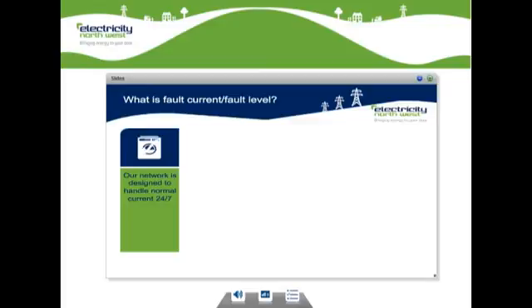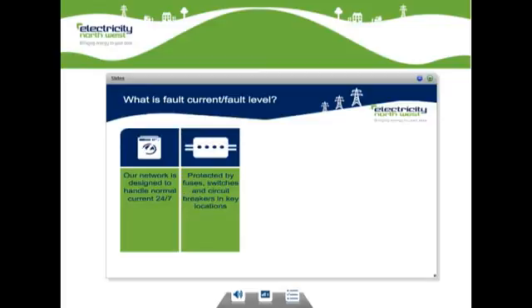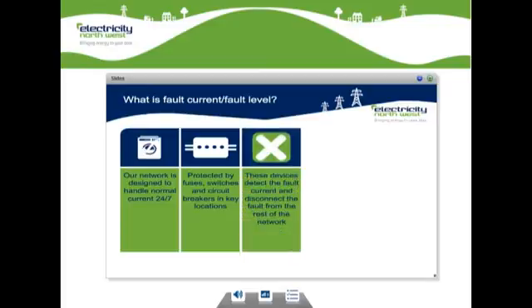So, a quick summary of what we mean by fault level. Our network is designed to handle normal current 24 hours a day, 365 days a year, and is protected by circuit breakers and other devices at key locations. When a fault occurs on the network, fault current surges towards the point of fault from all the sources of generation. This fault current is much greater than normal current and places stress on all the equipment that it flows through. The protective devices all see this fault current and react quickly, so the fault's disconnected.